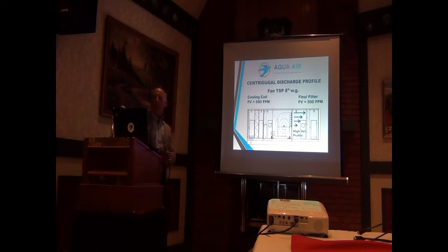When we talk about fans, we should also talk about the discharge profile and why it's important. If you look at this housed fan, what we were talking about originally with the forward curve and sometimes backward inclined curved blades, this is that base that I was talking about. It would be mounted with isolation. You've got your motor. We don't show the belts in here. That's where the drive losses would be added. But when you talk about the discharge profile, these lines here are upstream of the fan. This fan is spinning very, very fast. One of the rules of thumb in HVAC whenever you're designing a system is 500 feet per minute. Everything else in your air handling unit, your coils, your filter banks, even the air handling tunnel itself, is designed to 500 feet per minute.